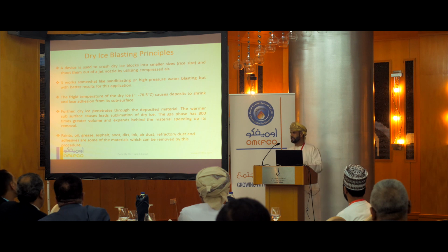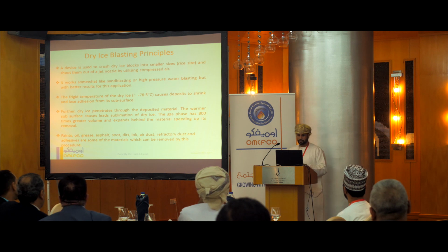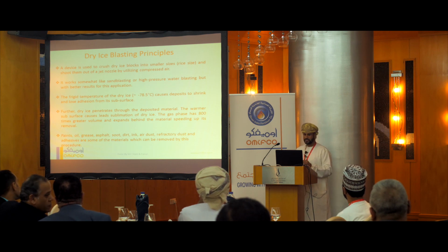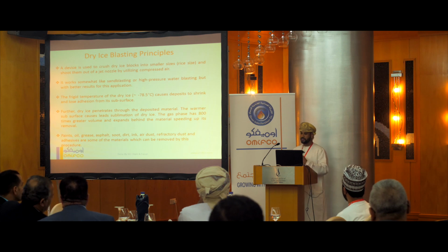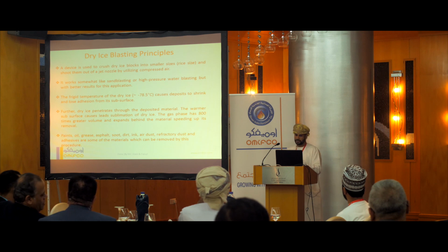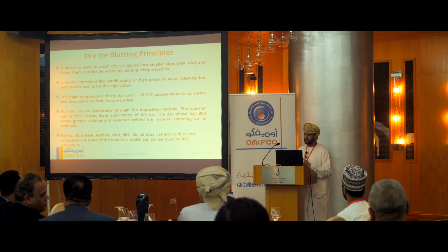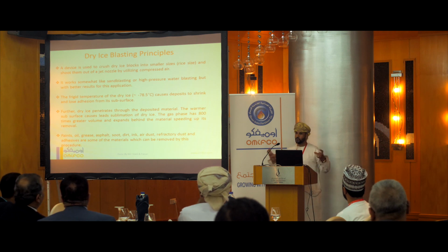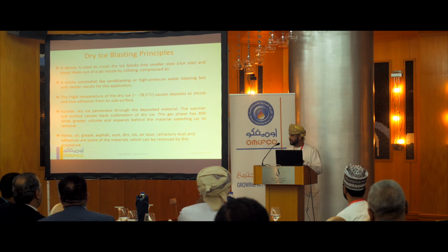Normally, it is the change from solid to gas directly without any liquid phase. Sublimation. The gas phase has 800 times greater volume and expands behind the material, lifting it up to remove any dust. It can remove paint, oil, grease, asphalt, soot, dirt, and refractory dust. Most of what deposits on those coils is refractory dust, and the dust coming out from the burners.